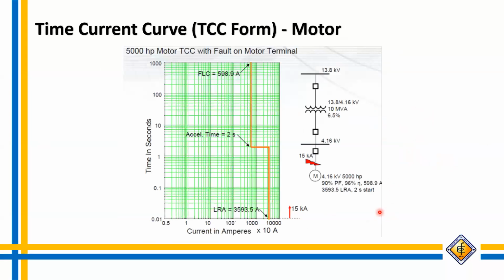For the motor damage curves, later we will also have an example, but the behavior of the motor during starting or cold start, it will generate an asymmetrical value, okay? The asymmetrical value will then pick up to an accelerating time, depending on the motor nameplate. Sometimes 2 seconds, sometimes 5, 8, or 10. For this example, it accelerates at 2. So it will decay to a continuous current, the operating current, or what is called the full load current. If it does not decay, as you can see in this example, it does not decay going to the full load current. You should have protection here, for example the overload relay, just to intercept the fault current or the overload current. Later, there is an example of that. I hope my plotting turns out nice later.